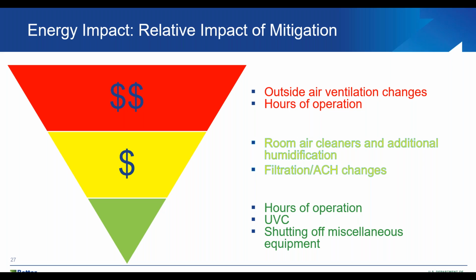If you're just replacing the filters and you're going from a MERV 8 or MERV 11 to a MERV 13, you may not see a significant increase. You'll see a little bit of an increase in terms of energy cost. But again, where there are additional costs, there's also opportunity to shut things off, so you get some additional savings from that. It's hard to put a specific number on it because some people may only increase it, like I said, 20 to 40%. Some may try to bring in more.